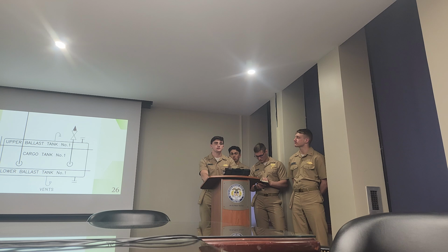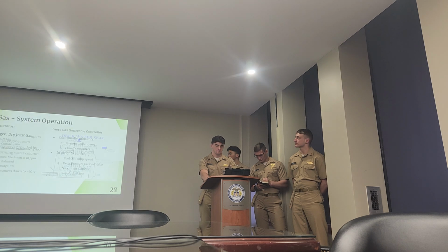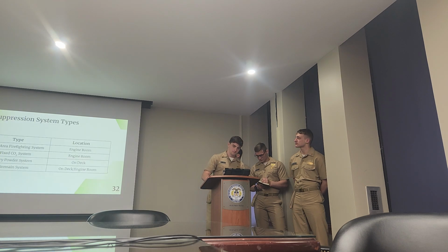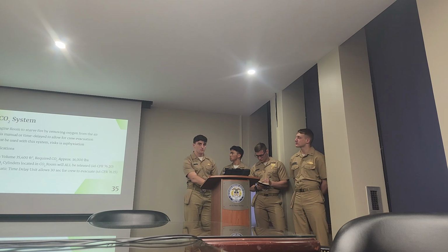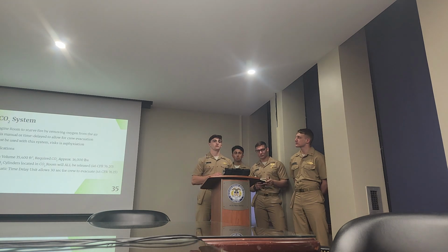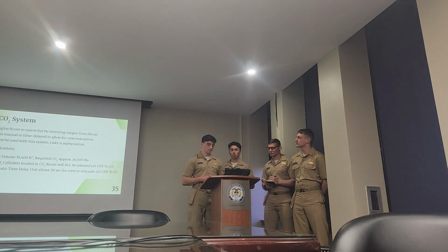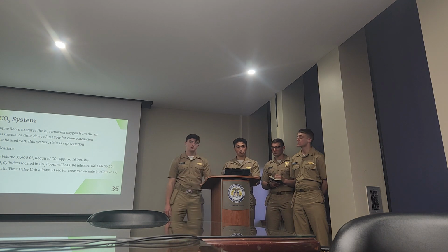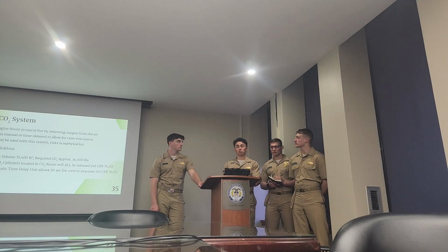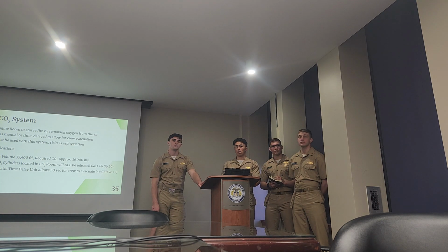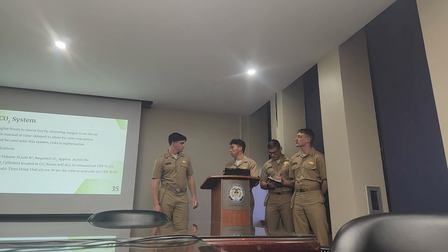And in the fire system, for the fixed carbon dioxide system, how many tubes do you have there? Did you mention that? How many nozzles in the fixed carbon dioxide? There should be 62 total nozzles. So did you mention it there? I did not mention that. Okay, you should mention that, sir.